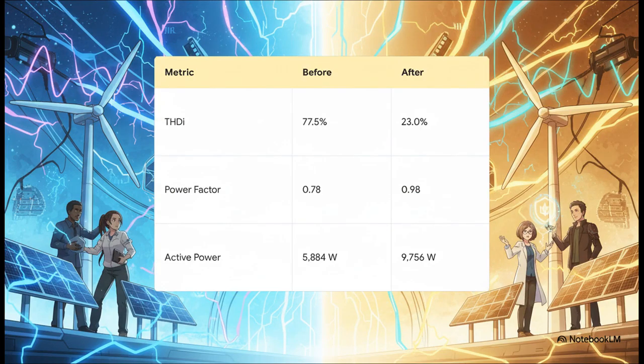Now let's look at an even more critical situation: a data center's power supply. Before, harmonic distortion was at a wild 77.5%. Afterwards it dropped dramatically. Now look at the power factor—basically an efficiency score for electricity, where 1.0 is a perfect A+. It went from a mediocre 0.78 to a near-perfect 0.98. That meant the system wasn't just wasting less energy, it was able to deliver way more clean, usable power to the servers that needed it.